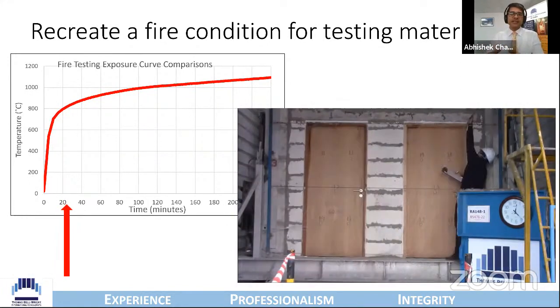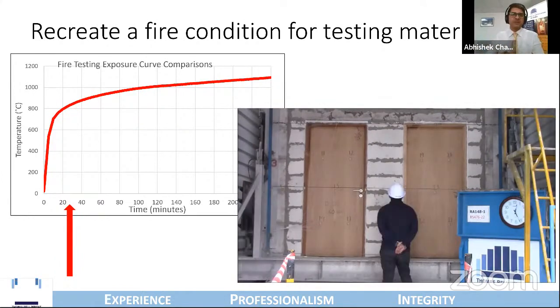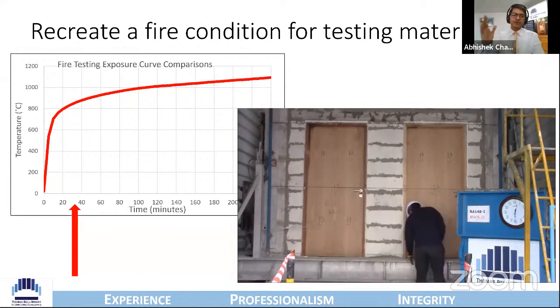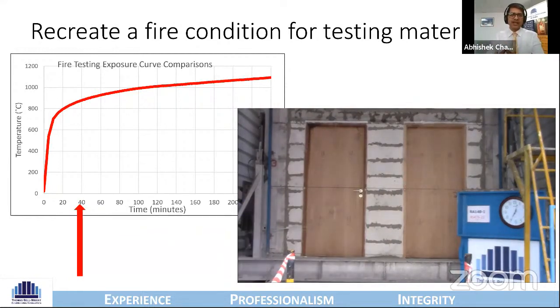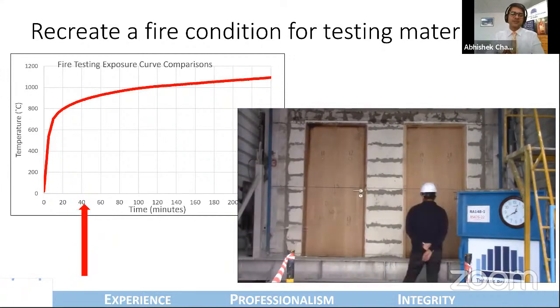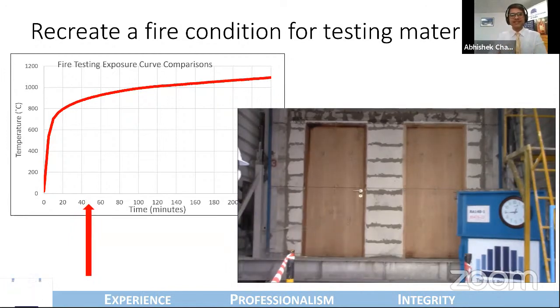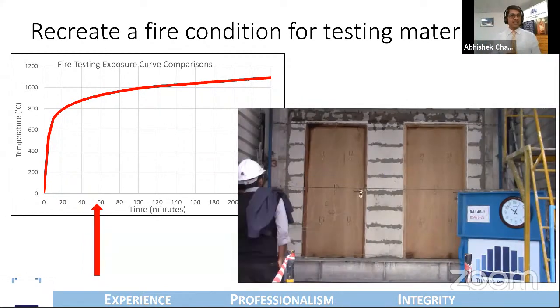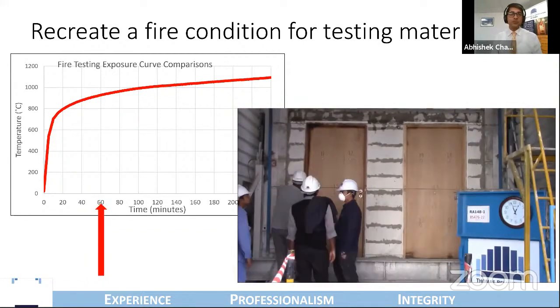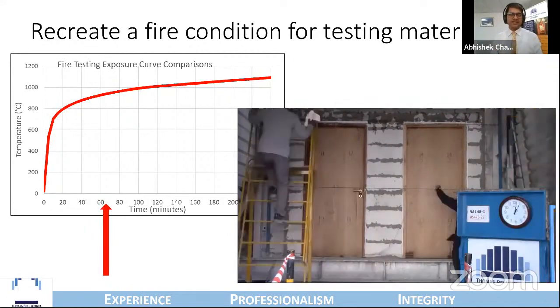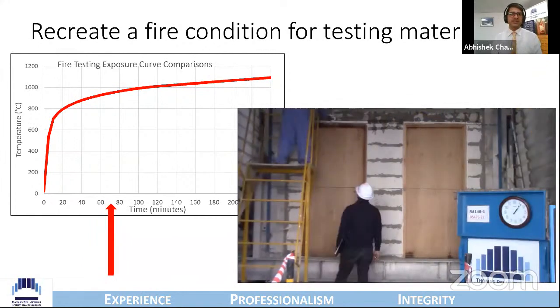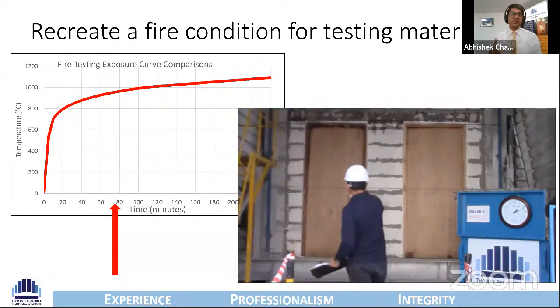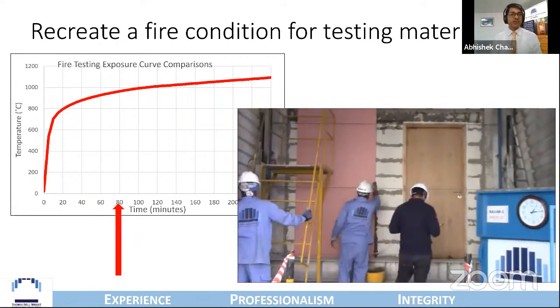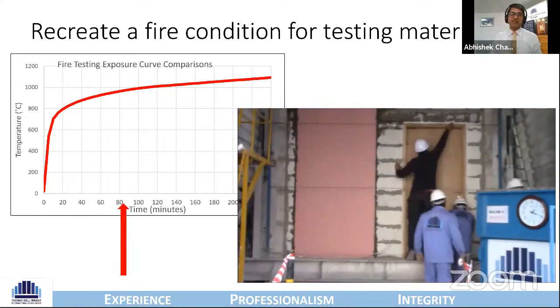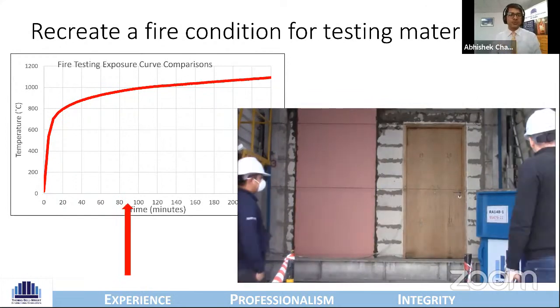Inside the furnace, we recreate a fully developed fire situation, meaning temperatures upward of 600, 700, 900 degrees Celsius, as well as positive or negative pressure. The graph shown indicates the rate at which the temperature on the fire side of the furnace increases over time. This is typically how any system, product, or material that claims to be fire rated, meaning it can contain and resist fire, spread of hot smoke and gases, and sometimes even insulation properties, is tested for 60 minutes, 90 minutes, 120 minutes, and so on.